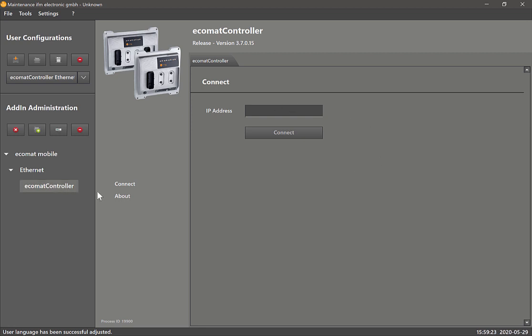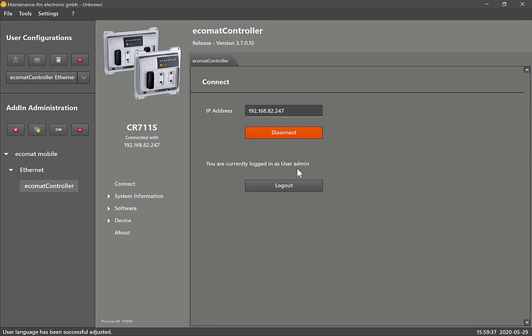Right-click, load add-in, and now you select Ecomat controller. Now you will see we've got this first interface for the Ecomat controller. By default the IP address for these devices is 192.168.82.247.